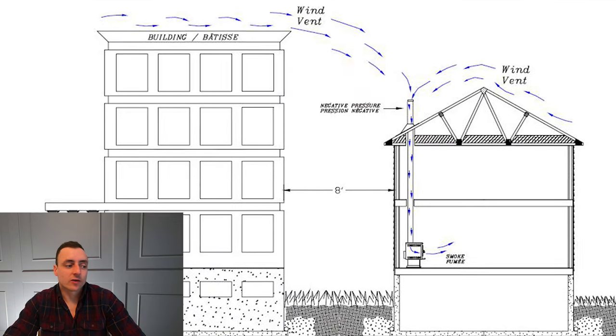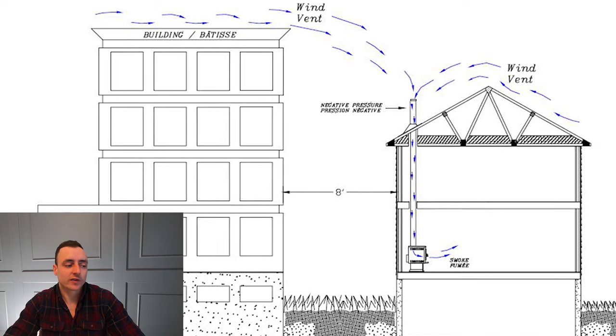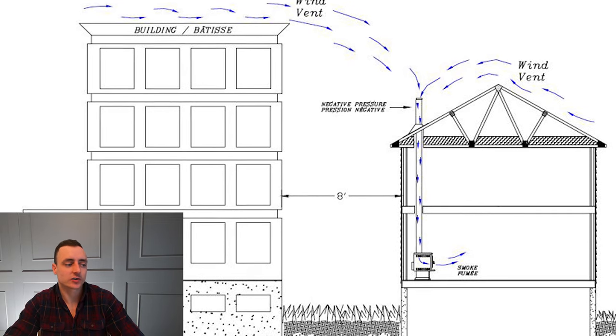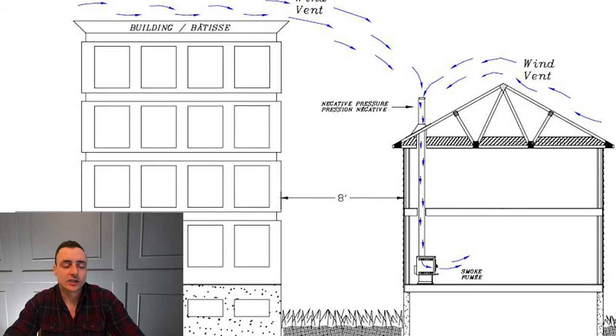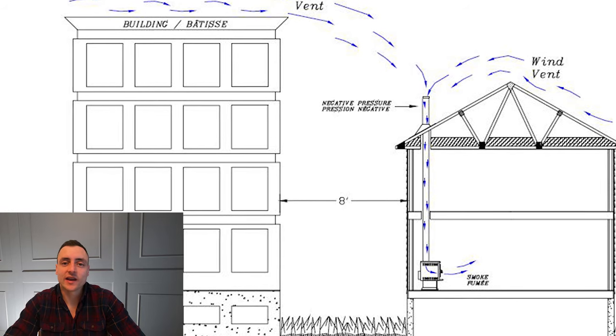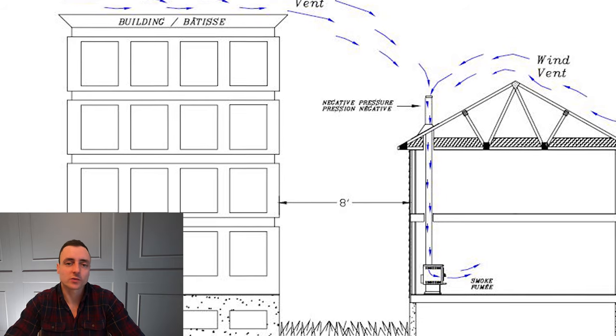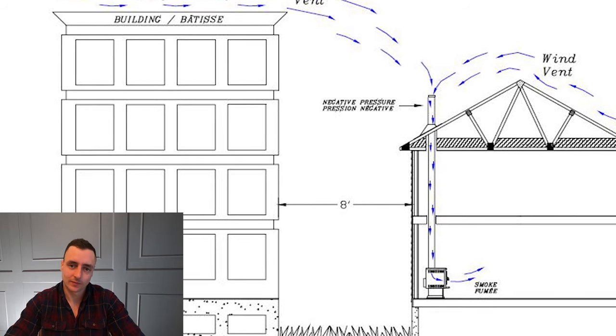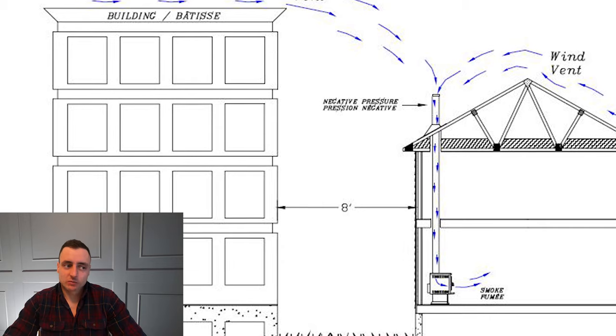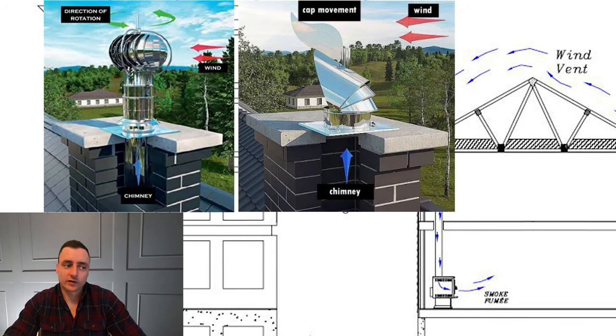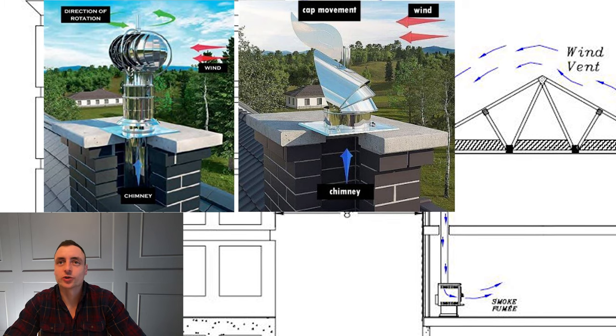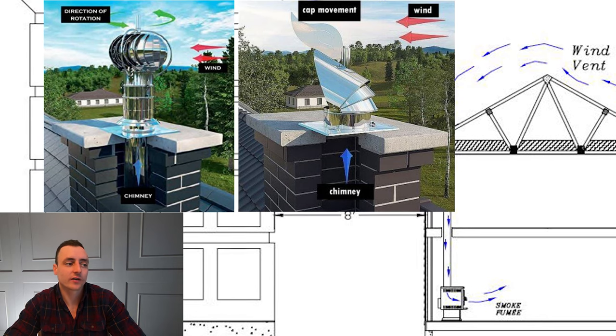Our fourth scenario shows the negative pressure effect caused by wind influenced by a nearby structure, such as this building here. If it's a windy day and you're not sure why smoke is entering the room, this could be a major factor. Some stoves are equipped with deflecting devices at the top of the chimney, which tend to reduce this wind effect.